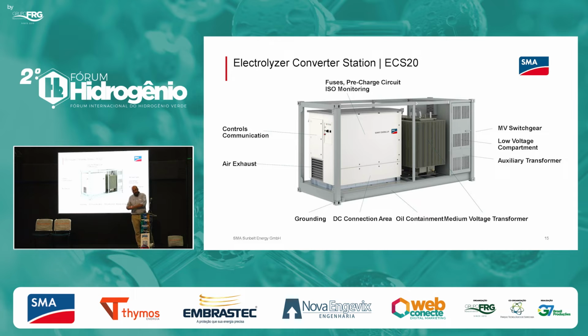You only connect the cable for the AC side, and it's the same for the DC connection—connect the cable and you can already start producing hydrogen. This is a 3 megawatt solution off the shelf. We've sold over 2,000 of these stations across different markets—PV, battery, hydrogen—worldwide, meaning we know how to connect these stations to grids worldwide regarding regulations, standards, and operation.